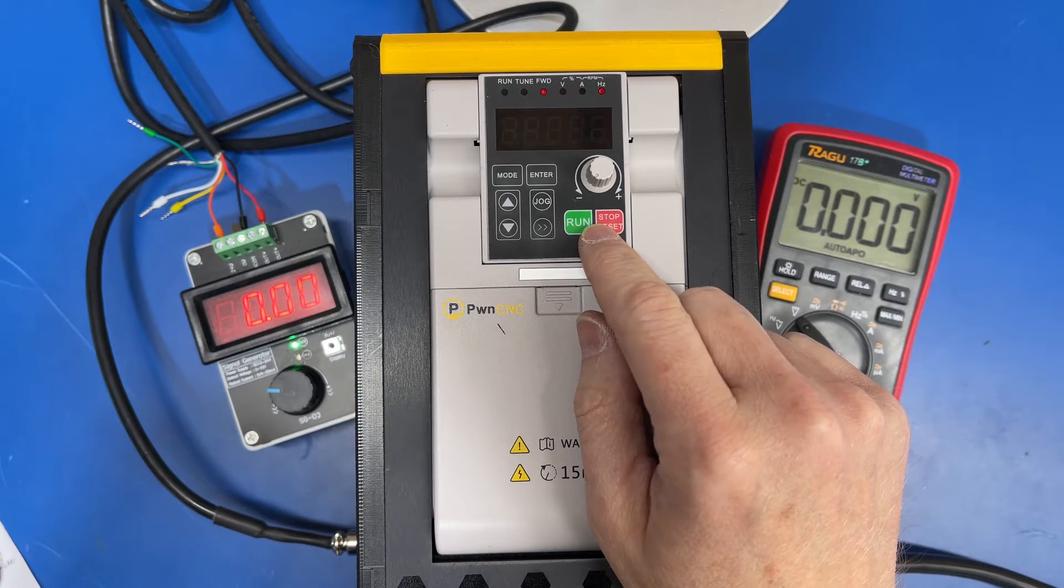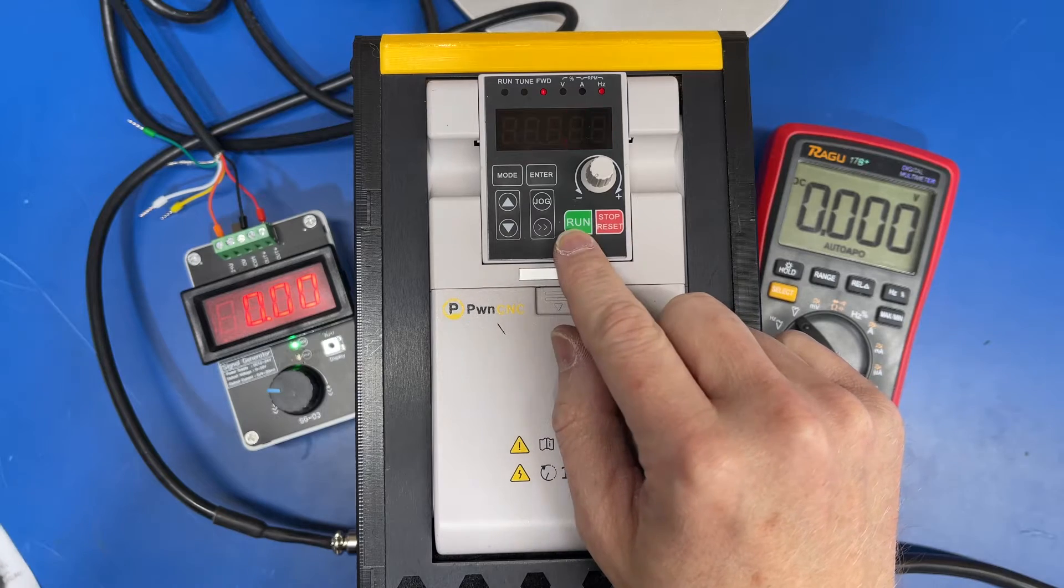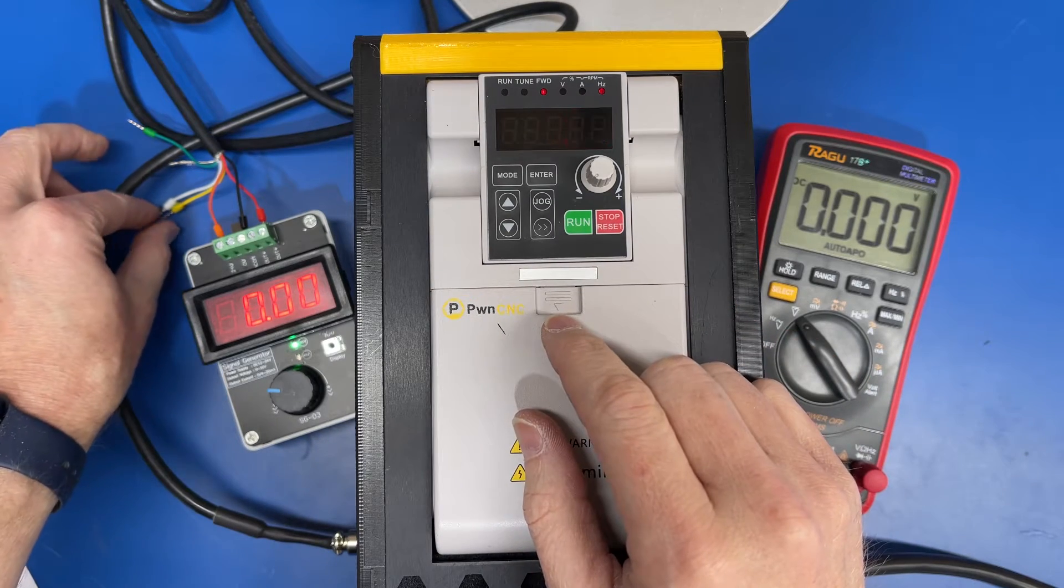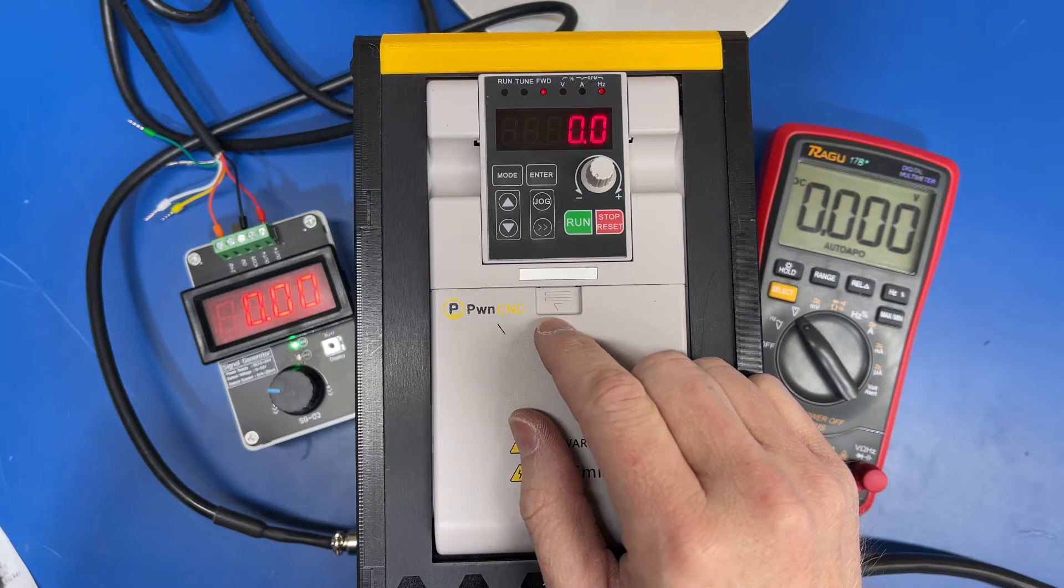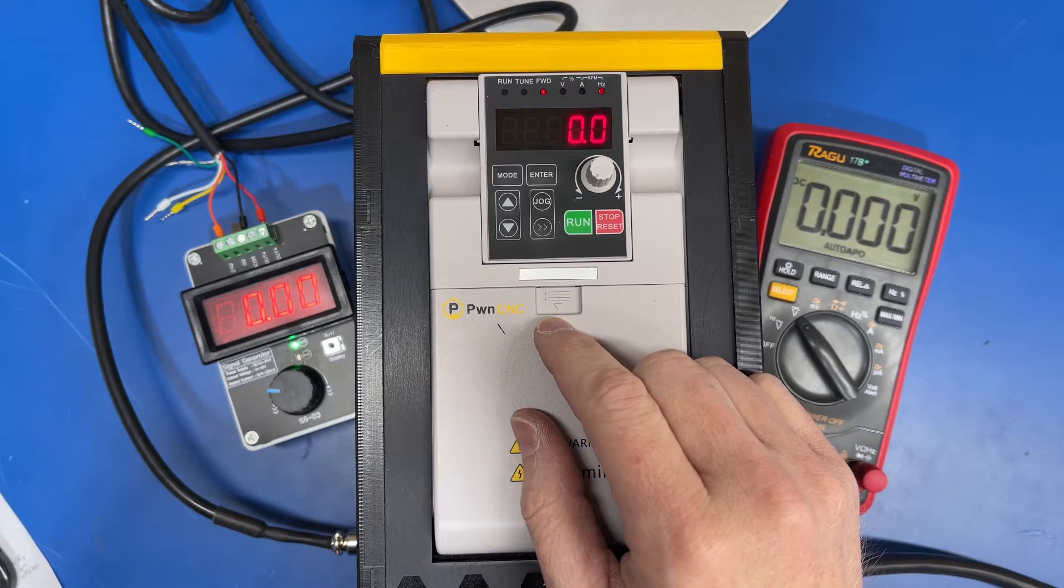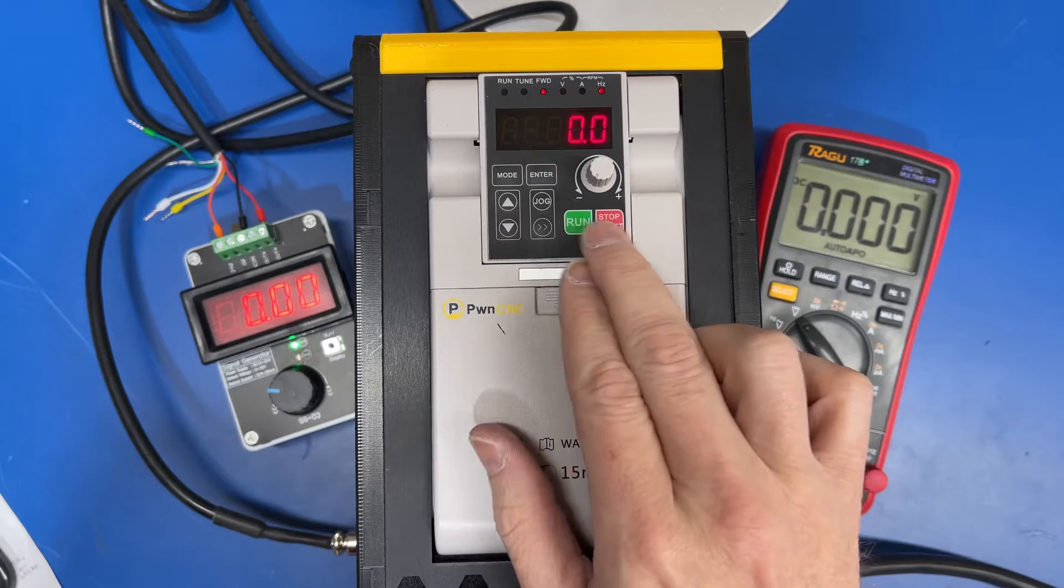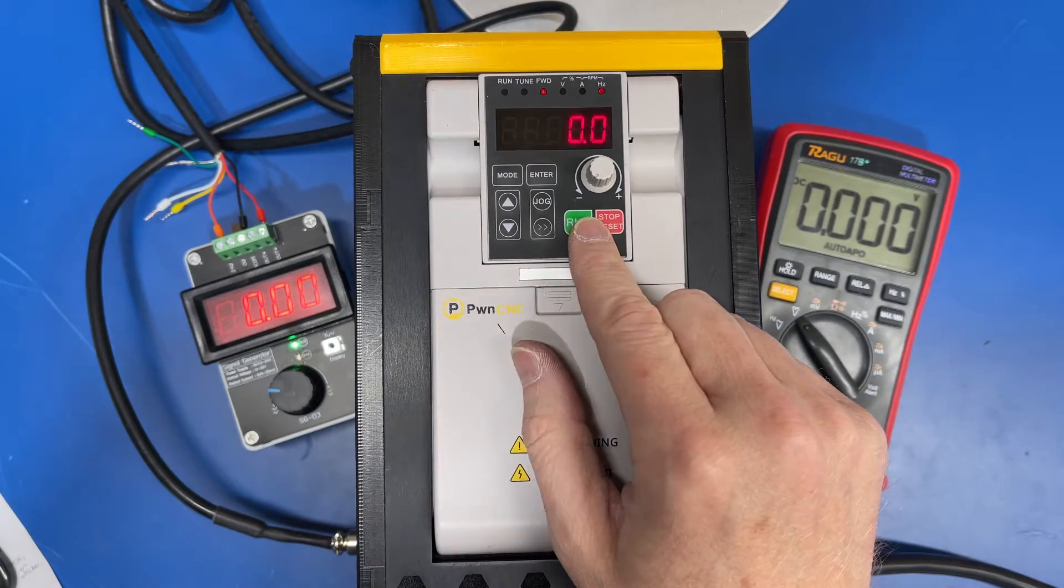I'm sorry, it's set to 0. Normally we set that to 1 so that connecting these two wires through a relay will trigger the forward function. We have it set to 0 so that it enables the run and stop buttons on the VFD keypad itself.